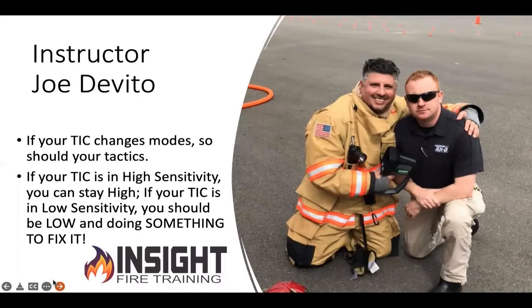Don't ignore it. Half the time when I debrief firefighters after close calls involving thermal imaging cameras — which I've done two in the last month where firefighters were burned — I asked them what mode was their camera in. They said, 'What do you mean?' I said, was it in high or low sensitivity? The answer I got was: I don't know what you're talking about.